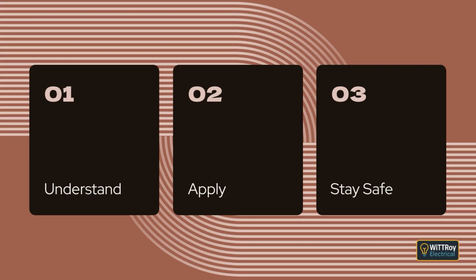Exposed conductive parts of the source of supply that are earthed must not be accessible at the same time as exposed conductive parts of the separated circuit. A protective device must disconnect the separated circuit automatically if faults expose conductive parts to different potentials. If the device is a circuit breaker, it must open all unearthed conductors at the same time.